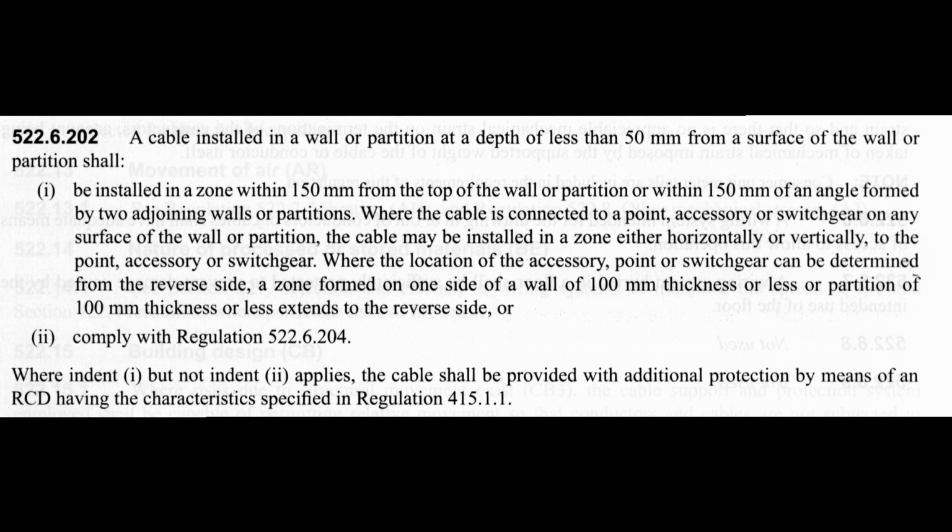So this really applies to any cable that's concealed in the wall, as in you can't actually see it. This is not applicable to cables on the surface or those in trunking or whatever else, because of course you can still see where they are installed. Now, if you're going to put cables in the wall, that is pretty much one of the things there.